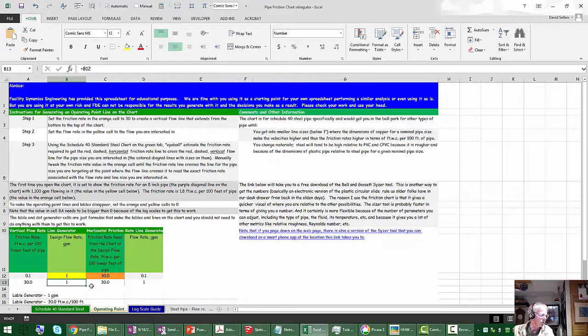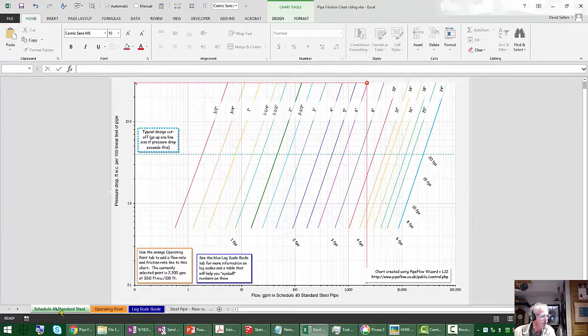And basically what you do is you start out by putting in the flow rate you're interested in. The instructions tell you this, so I'm going to put in 2200 GPM because that's the total for the two distribution pumps, okay? And then you click onto the friction chart tab, and basically what you just did was set this red vertical line, okay? Designers will pick a pipe in our industry so that the friction rate is typically 4 feet per 100 or less. Now you can be more sophisticated about that.